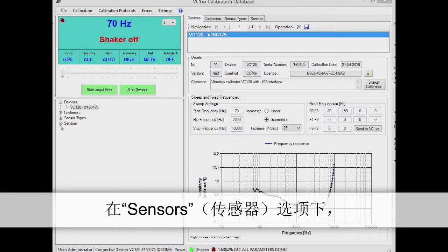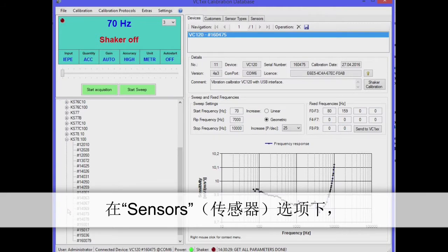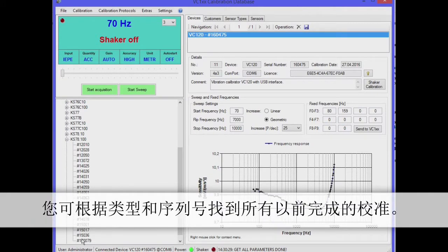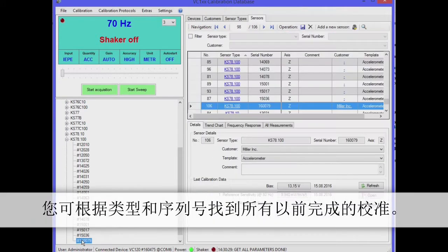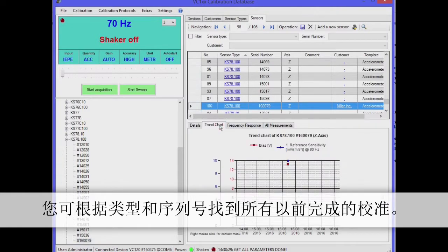Under Sensors you can find all previously completed calibrations sorted according to type and serial number. Here you can compare the last calibration with previous calibrations and produce trend reports.